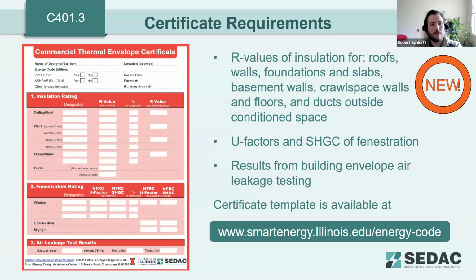All right, so next, this is a new requirement for commercial buildings within the 2021 IECC. If you're familiar with the residential requirements, this will look familiar to you. The commercial provisions are now requiring a commercial thermal envelope certificate to be permanently installed within the building upon completion of construction. Typically, this is going to be located within a mechanical room, potentially an electrical room near the main electrical panel, something like that, in a location that's easy to see and is not going to get covered up by other information.